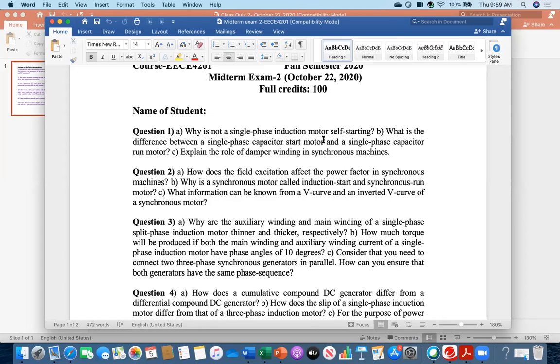What is the difference between a single-phase capacitor start motor and a single-phase capacitor run motor? In a capacitor start motor, the capacitor is only for starting purpose — once the motor achieves about 75% of synchronous speed, it is disconnected by a switch. In a capacitor run motor, the capacitor remains always connected with the auxiliary winding circuit during both starting and running — 24 hours connected.